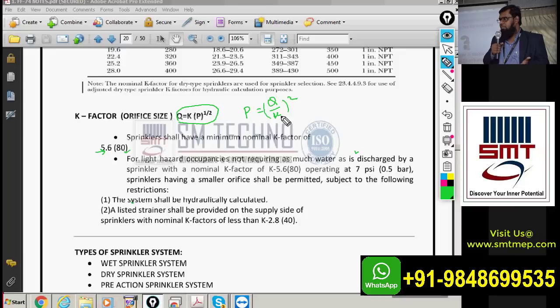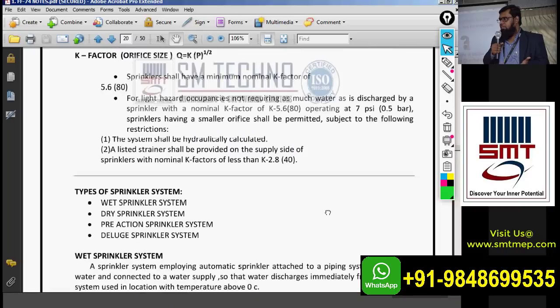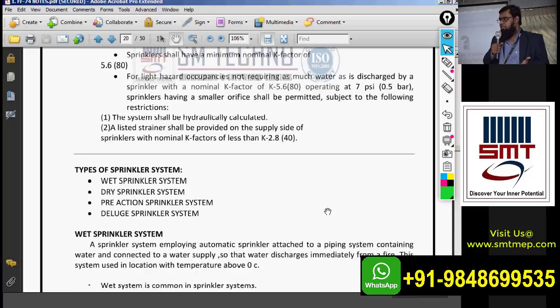These formulas are used to find pressure or flow rate Q. Also highlight that the minimum operating pressure per NFPA guidelines is 7 psi. After calculation, if the pressure is more than 7 psi we take the calculated value; if less, we take 7 psi as the minimum.